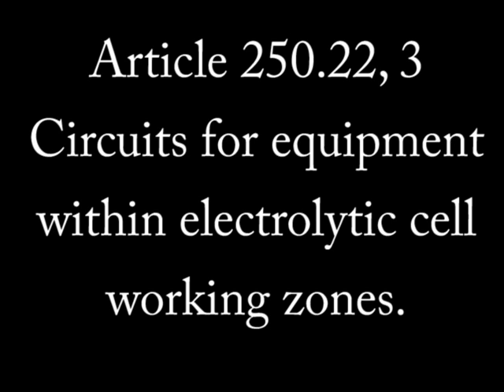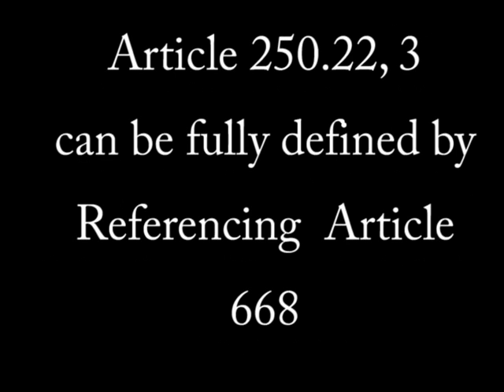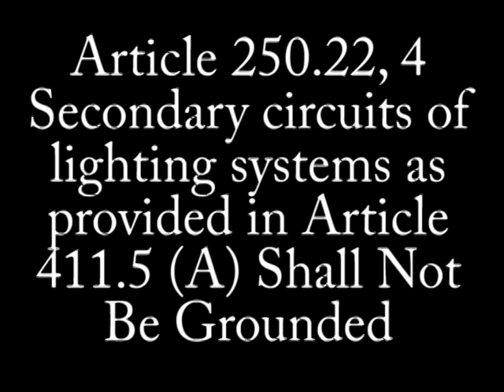Part 3: Circuits for equipment within electrolytic cell working areas shall not be grounded. Simply, factories that use electrolysis to make a variety of metals or produce hydrogen gas in the process are not to be grounded. A more exact definition can be found in Article 668.